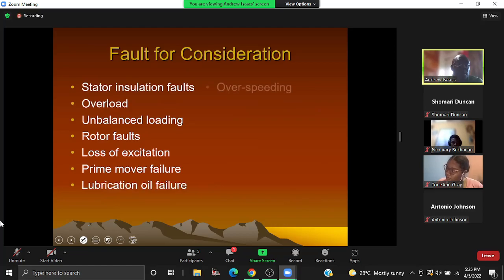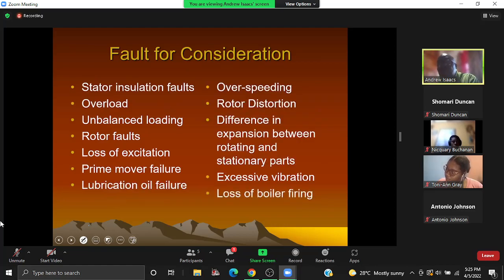Just listing here some of the issues that can impact your generator. We're talking about insulation failure, overloads, unbalanced loading, rotor faults, loss of excitation, and obviously if we're dealing with a synchronous machine, prime mover failure. So if there's an issue with your turbine, then you need to know that. Because if there's a problem with the turbine, the generator won't trip immediately, but your generator will start operating like a motor. So instead of supplying power to the system, it starts to absorb power from the system. Okay? Lubrication failure.